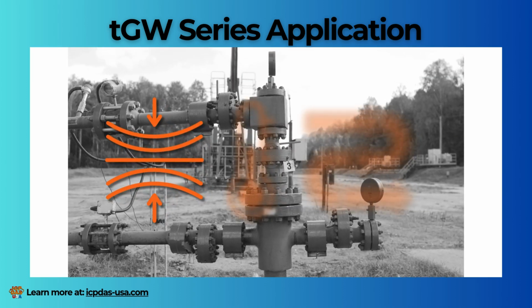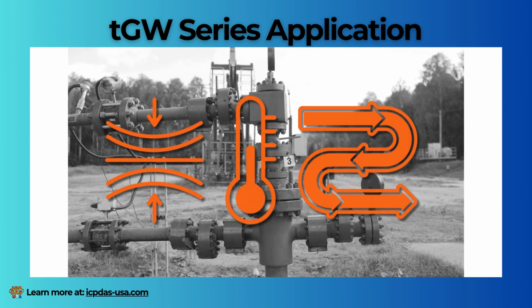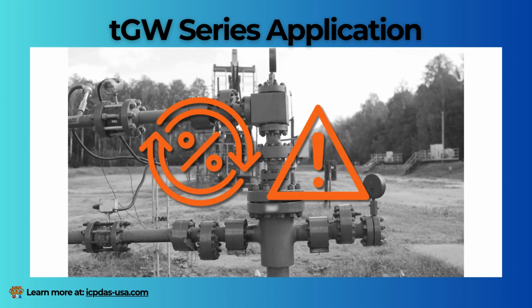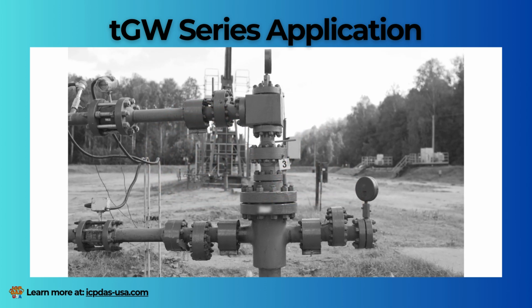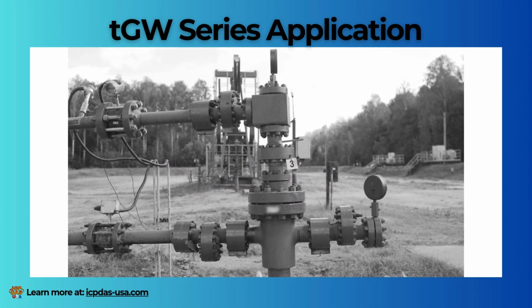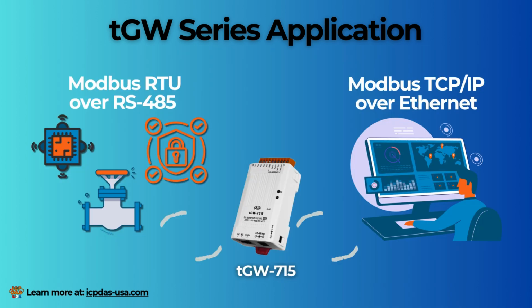At the wellhead, sensors continuously measure pipeline pressure, temperature, and flow. Valve actuators adjust flow rates, and gas leak detectors ensure safety. All of these devices operate on RS-485, transmitting data using Modbus RTU. The tGW 715 acts as the bridge between these field devices and the control center. It converts Modbus RTU signals into Modbus TCP/IP, allowing real-time data transmission over Ethernet or a wireless network. This data is then sent to an industrial switch, where it can travel via fiber optic cables or LTE, satellite connections to reach the SCADA system.